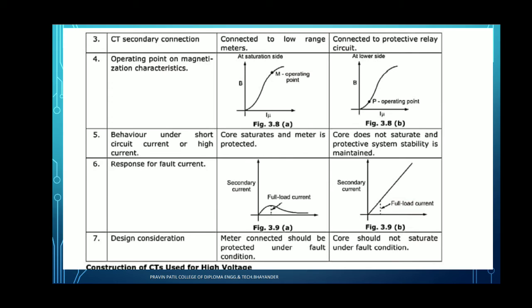Next difference is the operating point on the magnetization characteristics. On the magnetizing characteristics, point M, the operating point for metering, is at a large value, and point P, the operating point for protection, is low. Next difference is the behavior under short circuit current or high current. The metering current transformer core saturates, and the meter is protected. In the protection CT, the core does not saturate, and protection system stability is maintained with the help of the protection CT. But inside the metering or measuring CT, the core saturates and the meter is protected.